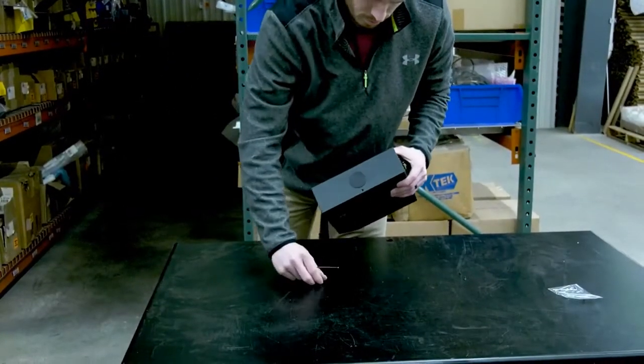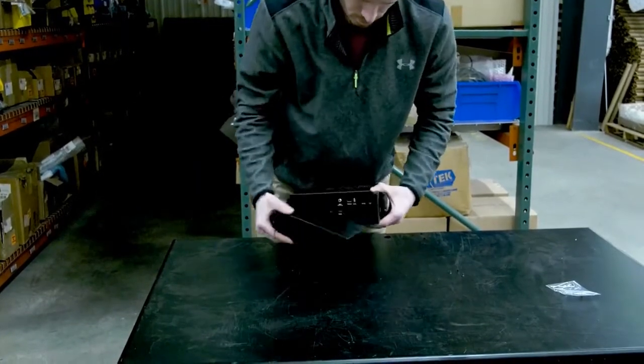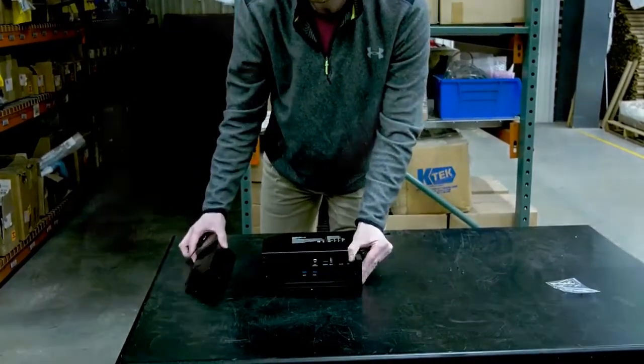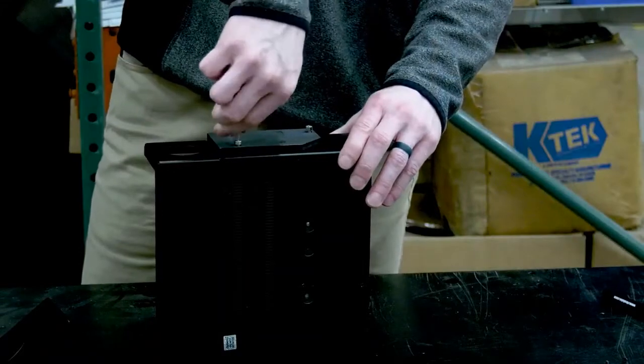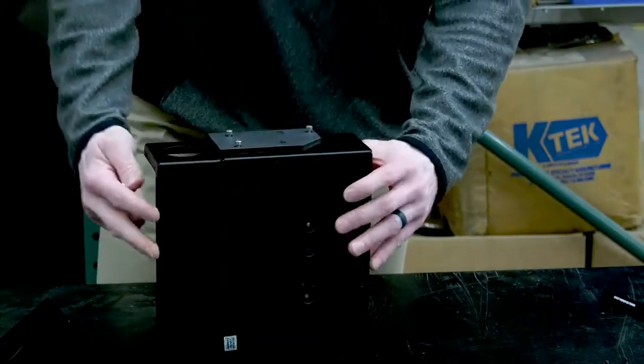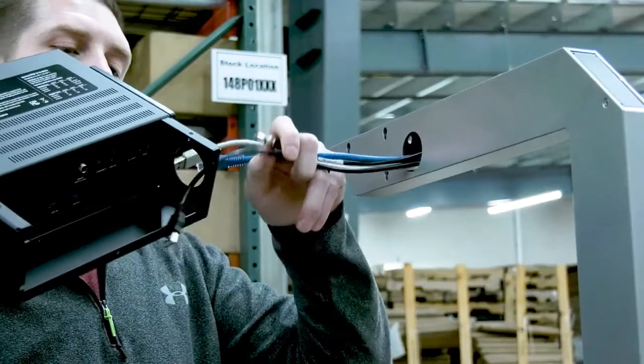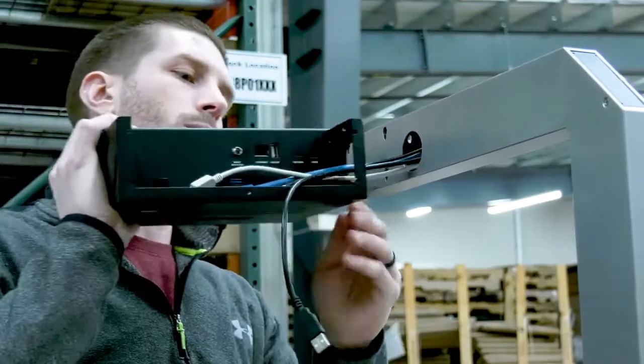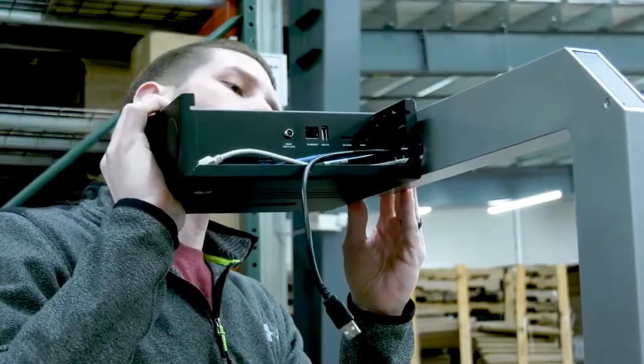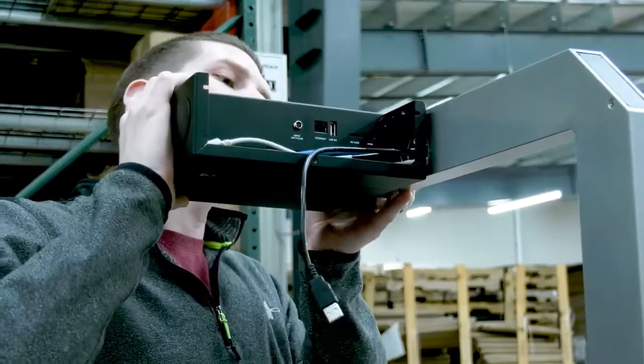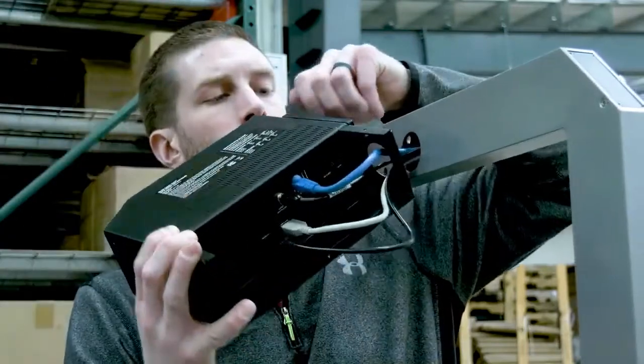Remove the rear cover from the scanning head. Loosen but do not remove the 3 mounting screws so they are approximately 1/4 inch from the spacer plate. Insert cables from the upper pole assembly through the cable slot on the rear enclosure. Cable connections may also be attached now or later in the process.